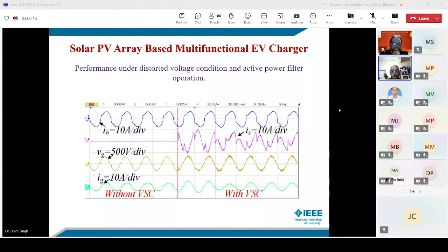So you must have a small generator also. We took a squirrel cage machine with a DG set, with the specific advantage that we force this machine, when connected, to operate in a fairly stable voltage mode with this converter. So this converter has a lot of responsibility - to improve the power quality of the grid when non-linear loads or vehicles are present, or with the DG set, so it does not draw harmonics or reactive power and also regulates the voltage in islanded mode.